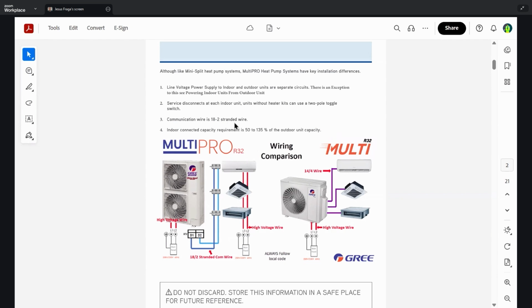The communication wire is 18/2 stranded wire. Does not have to be shielded, just stranded. And the indoor connected capacity requirement is the same as the 14A model. So you have to have a minimum of 50% and a maximum of 135. If you fall out of that window, the unit will not start and give you an error code. Depending on if you're low or if you're high, will be the error code that you see.